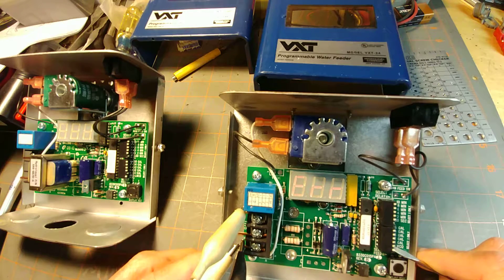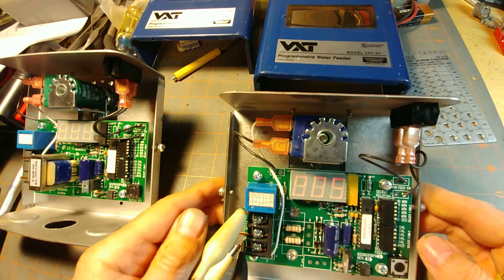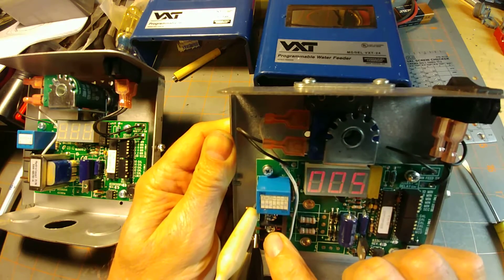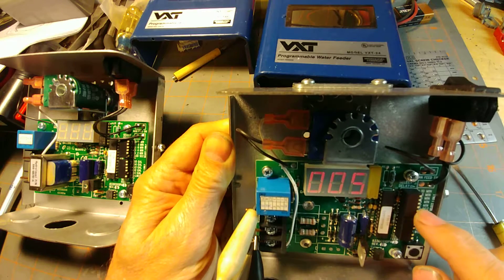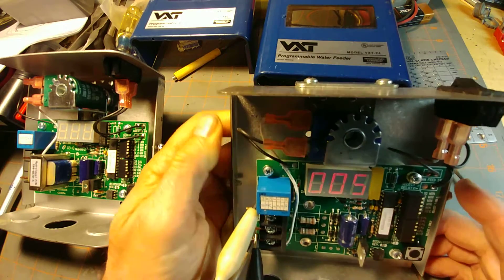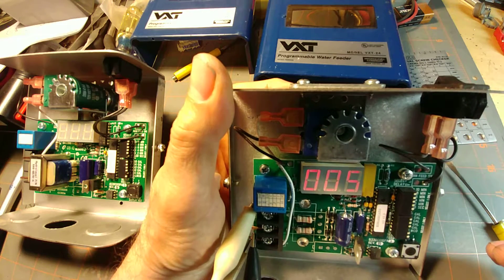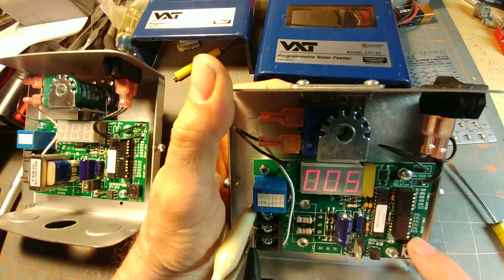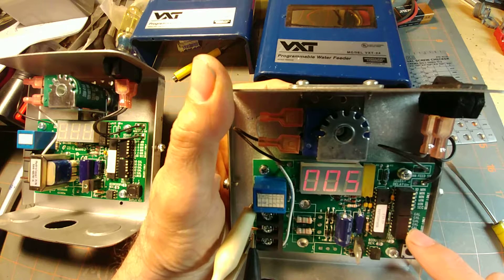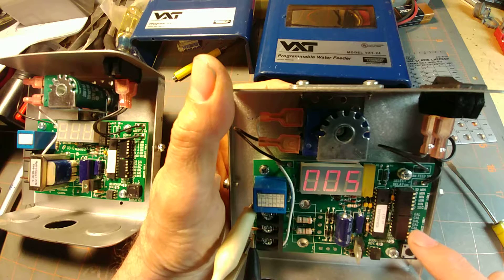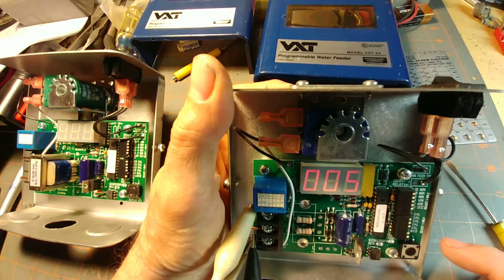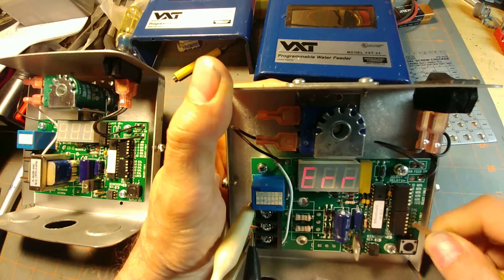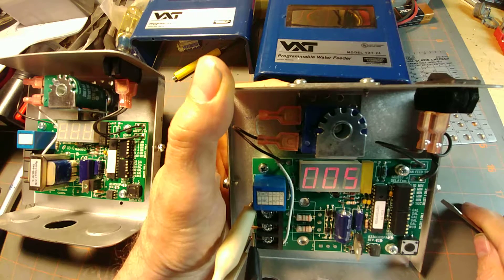What I would do is your best guess at first. Let's say you set it at 2 gallons. So it receives a signal, your delay is set at 30 seconds, perhaps as long as 2 minutes, and then it triggers and begins to feed. This is where you need to observe. You set your boiler to where the low water cutoff is triggered or just below that point. Then have this unit trigger and watch the boiler refill. If the refill comes to significantly less than half full, half the sight glass filled, then change your setting accordingly. You might have to go up on larger boilers, you might have to go up to 3 gallons or 4 gallons.